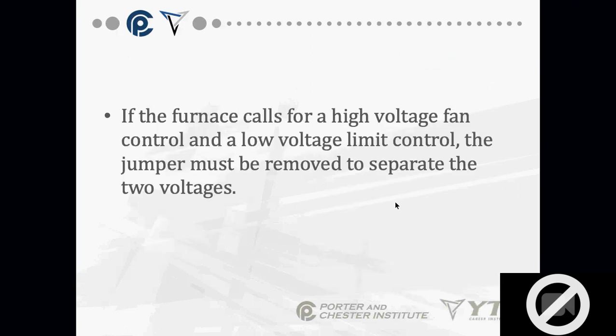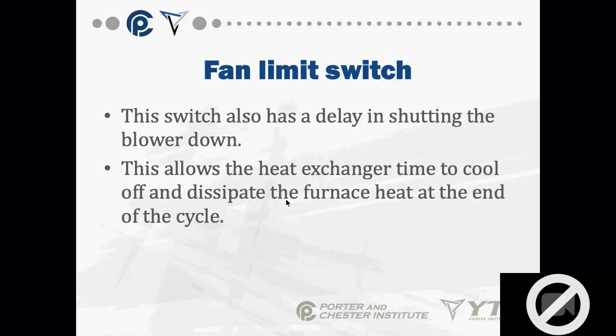If the furnace calls for a high voltage fan control and a low voltage limit control, the jumper must be removed to separate the two voltages. This is a very frequent setup. The fan control is on high voltage. Okay, line voltage coming into the fan. The low voltage side is your limit because that's where the burner controls are. Okay, that's where our primary control setup is. So we have the low voltage side having my high limit, high voltage side having the fan control, the blower control. We have to remove that jumper. I have seen people blow up primary controls because they forget to remove the jumper. Don't be Dave. Okay, I mean, don't forget to remove that jumper.